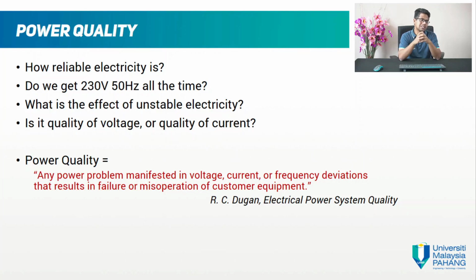Another question is whether it is about the quality of voltage or the quality of current. Although power means voltage times current, when we talk about power quality, normally we talk about the voltage. Why? Because the voltage is the one given to us by the utility. The utility provides voltage; the client is the one that draws the current. So in short, according to the Dugan book, power quality is any power problem manifested in voltage, current, or frequency deviation that results in failure or misoperation of customer equipment.